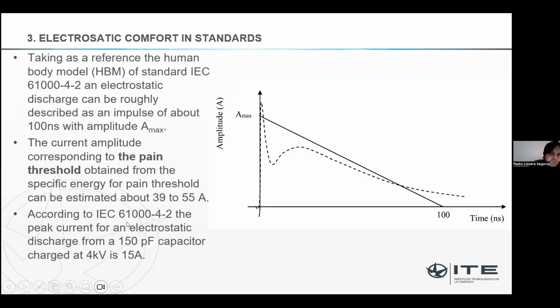As a reference, a 150 picofarad capacitor charged to 4 kilovolts is 15 amps. So if we consider that the perception threshold is 1-2 kilovolts, let's say this is below 15 amps, the current you can feel. Probably 10 amps or 5 amps, but we don't know. Okay, there's no information about this.